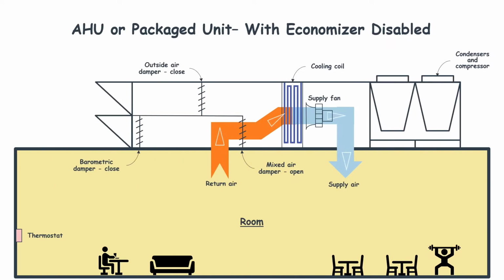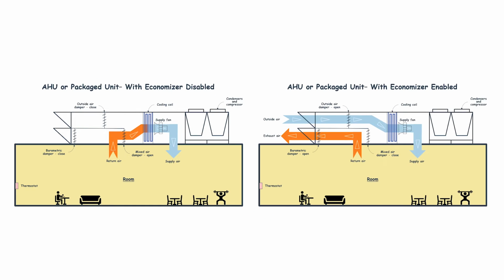Normally, an air handling unit or a package unit circulates the indoor air to cool it. The fans of these units bring in or return the room's air into the unit where it gets cooled down by a cooling coil. But when the outside air is cool enough, the units stop circulating the room's air, and instead start to supply outside air into the room. Since the outside air is already cool, the compressor of the mechanical cooling system can operate in low capacity or completely stop working. And that's how energy is saved with an economizer.